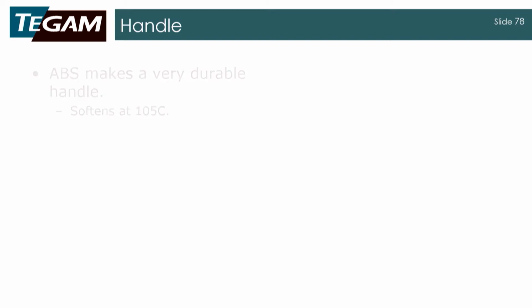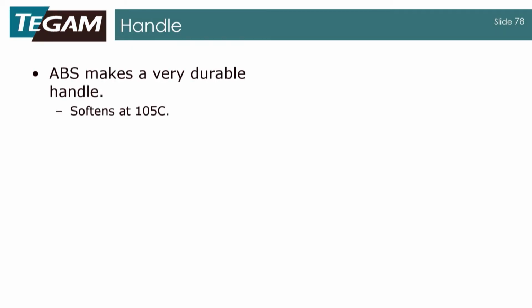So first, the handle. Pretty common handle is ABS plastic. You can make it ergonomic. They can mold and 3D print them now. One thing to take into consideration is that they do soften at 105 degrees C, but that doesn't necessarily mean that whatever you're measuring at 105 degrees C is instantly going to melt it. You have the conduction of your sheath, and the longer that is, the longer it's going to take for whatever you're measuring to work its way up to the handle. So really, when you're dealing with ABS, if you're taking quick temperature measurements, it'll work in many applications.